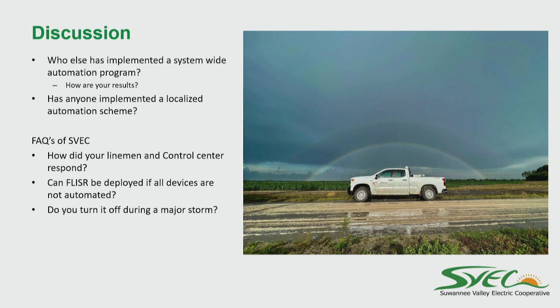Can FLISR be deployed if all devices are not automated? That it can be. We did this in sections. Our first section was deployed as we were deploying relays in the middle. They weren't on FLISR yet. We hadn't tested them, so the system wasn't controlling them until you go in there and turn that feeder on.